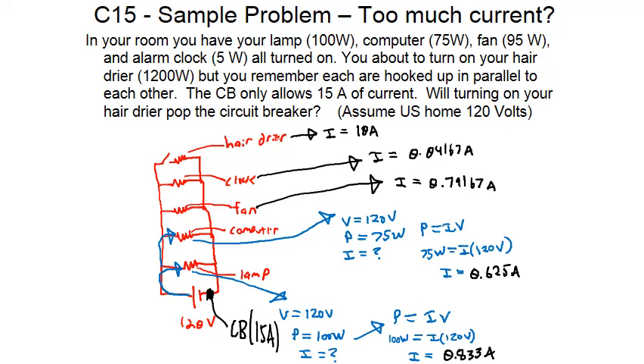The hair dryer would use 10 amps if we closed it. If we add them all up, that would actually be okay. We would be underneath the 15 amps of the circuit breaker, because in parallel, the current is splitting, and when it all comes back together, this is a full amount of 12.29 amps. Since it's under 15 amps, the circuit breaker will not pop.